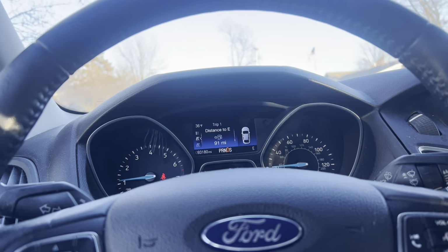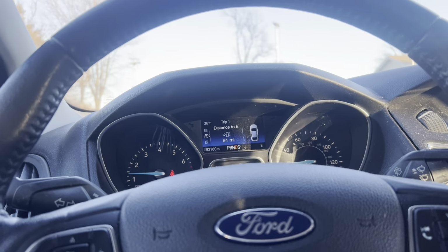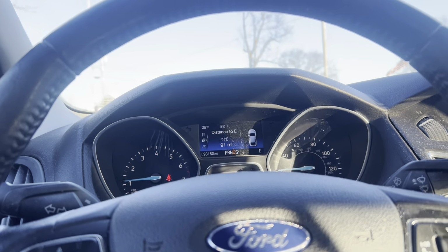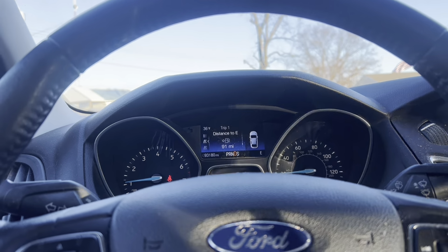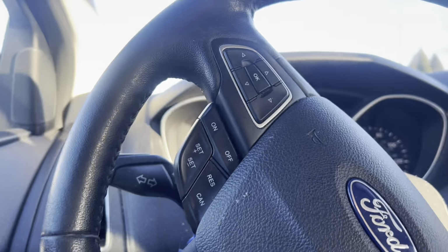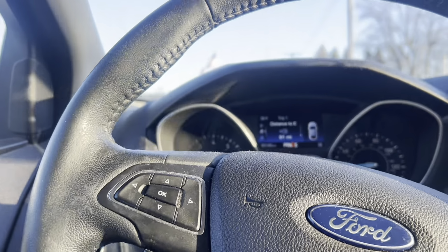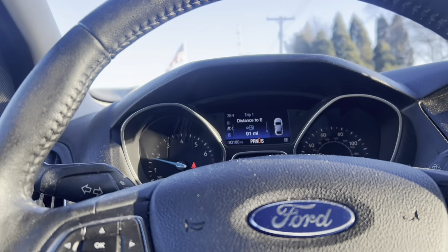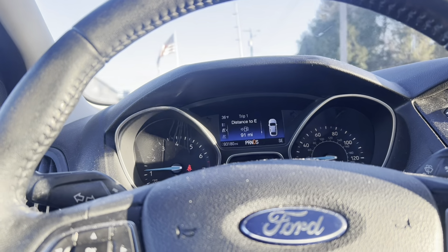That wraps up the service call. I spoke with my relative about what was going on. I informed them what I fixed, let them know on the filter. Everything else looked like it was in range. Temperature split was good and in range. Amp draws are good and in range. That's what it's like to run a service call and get stuff fixed and travel and all that good stuff.